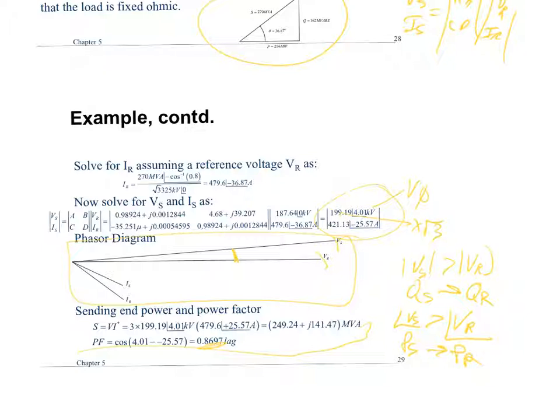This tells me that P, that 270 MVA, is greater than the surge impedance loading for this particular line, because I'm consuming VARs in the line, which means the power demanded is greater than the surge impedance loading. You want to do that for homework? Check to see if that's the case? Who says yes? We have a test tomorrow.